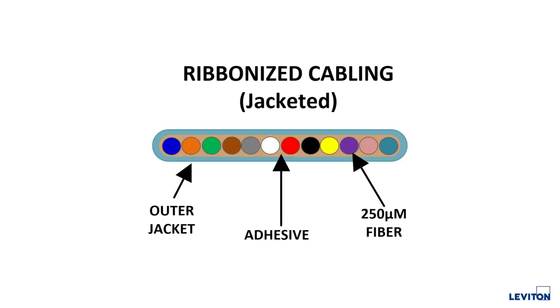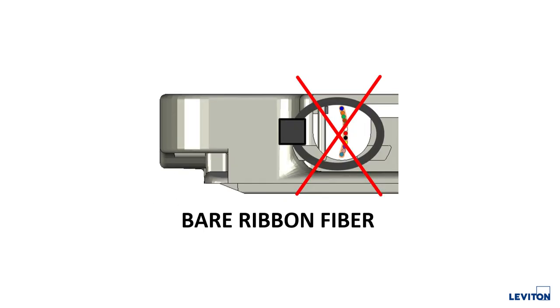If routing ribbon fiber into the module, all ribbon fiber must be furcated into tubing or a breakout kit. Routing bare ribbon fiber directly to the module may result in damage to the fibers.